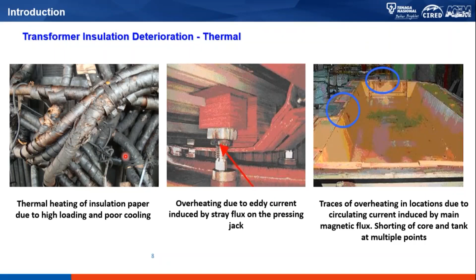in the middle photo there. Or on the left-hand side, as you can see, the thermal heating of insulation paper due to high loading and poor cooling causes the insulation paper to be very, very brittle and easy to fracture once there is a movement of the windings, perhaps due to a short circuit fault, whether very near or a distance away from the transformer.